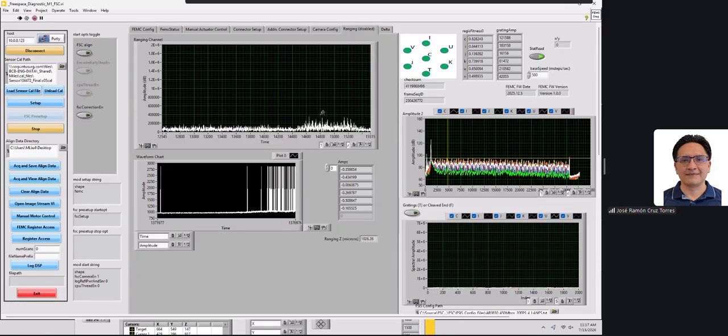And then there's usually one MC5, and one MC5 can only support one ranging collimator. But Joel had an artifact made which splices 6 collimators together at different path lengths. So instead of having one big peak on a single channel, it'll be 6 equally spaced out peaks. So you can mount 6 different collimators and do that with that MC5.